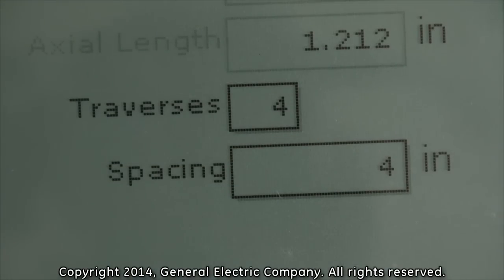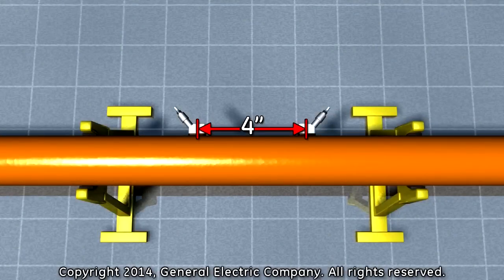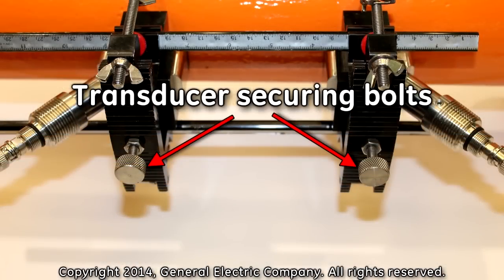The number of traverses is 4, which means you will place the transducers on the same side of the pipe, and the spacing is 4 inches, which means you will place the transducers 4 inches apart from the center of each transducer securing bolt.